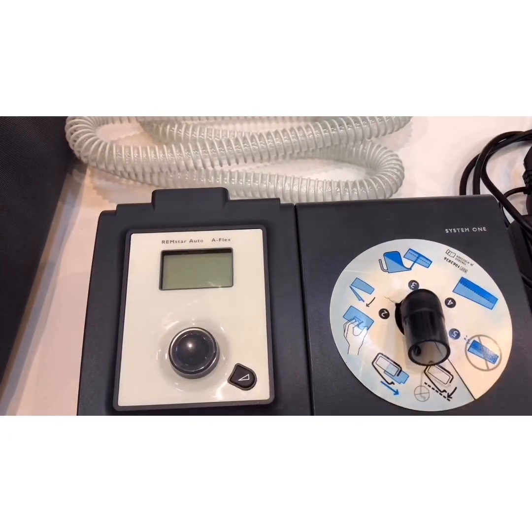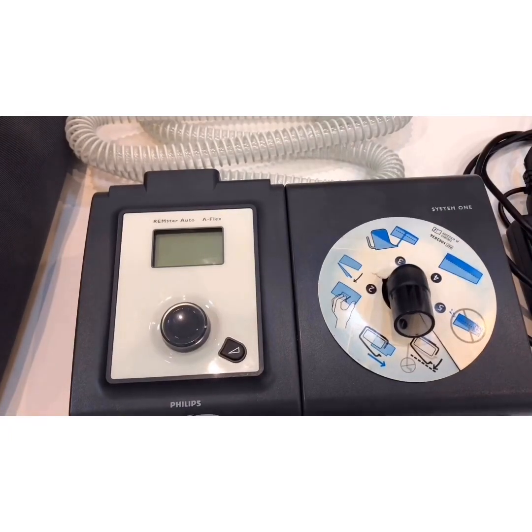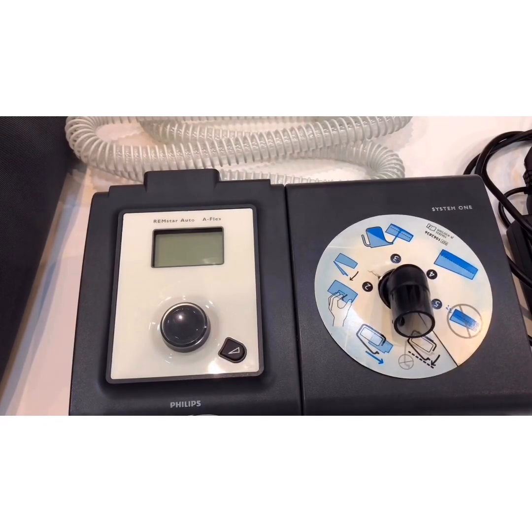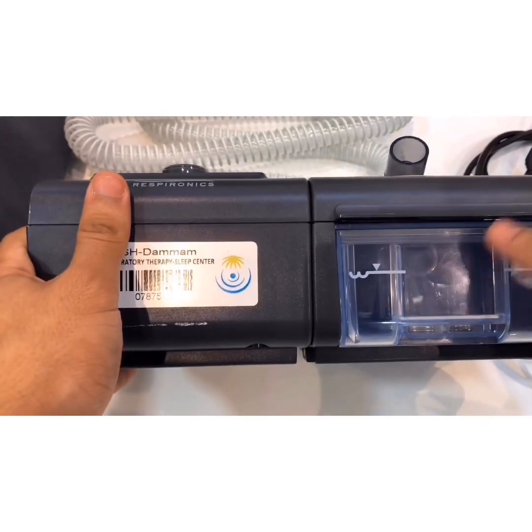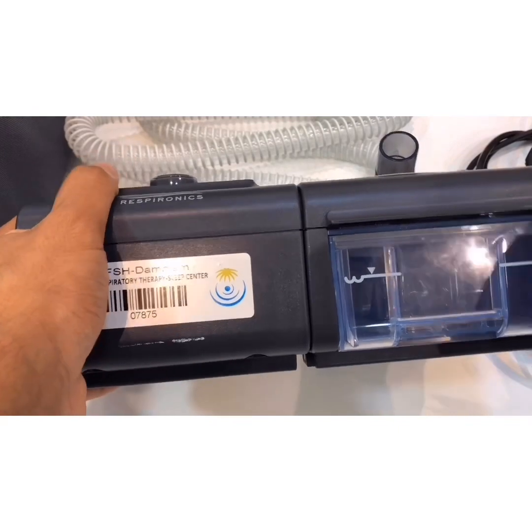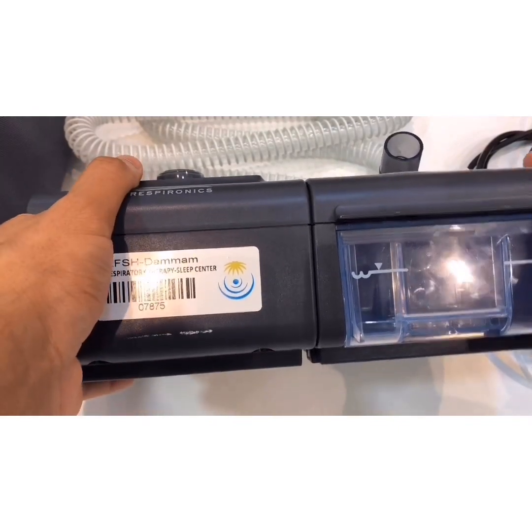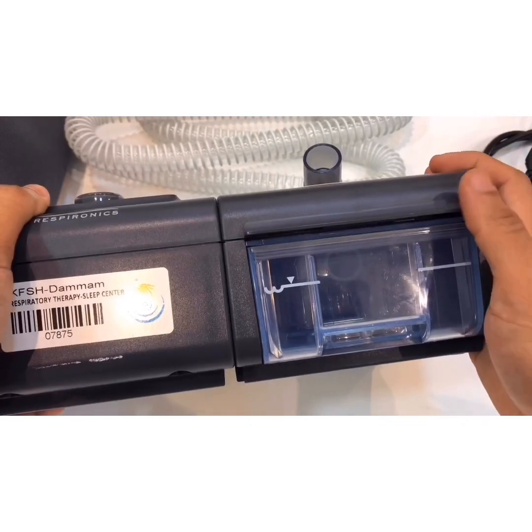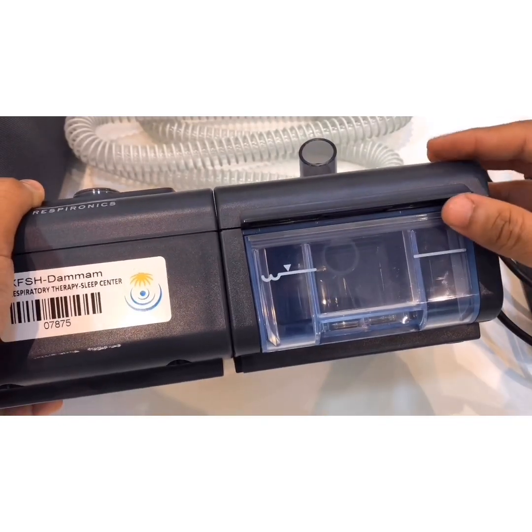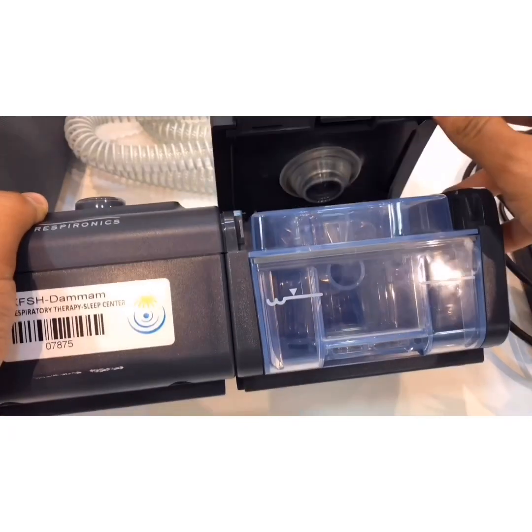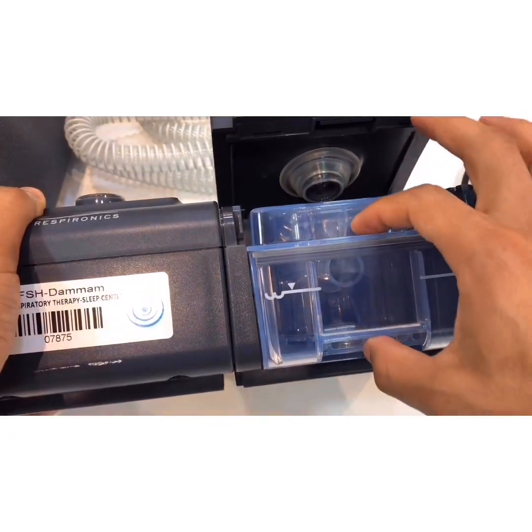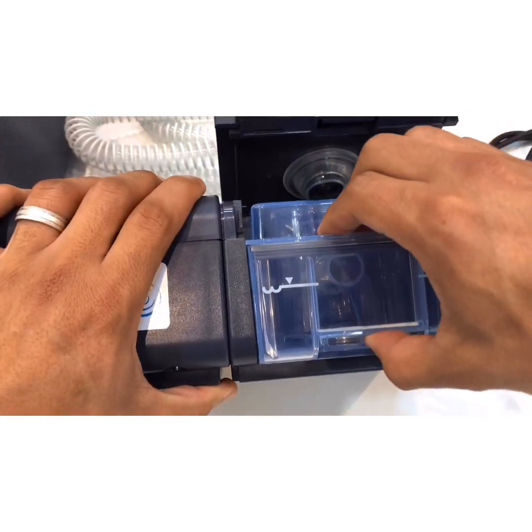This is the air outlet. If we are going to use the water humidification chamber, this will be the air outlet. Regarding the humidification, some patients like water chamber humidification, and this is the location of the chamber. It will be in this area. If we want to fill the chamber with water, all we have to do is pull this back, then it will open. Then this is the chamber. All you have to do is slide it out.